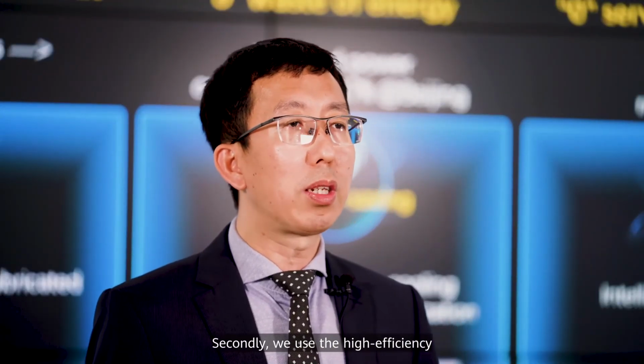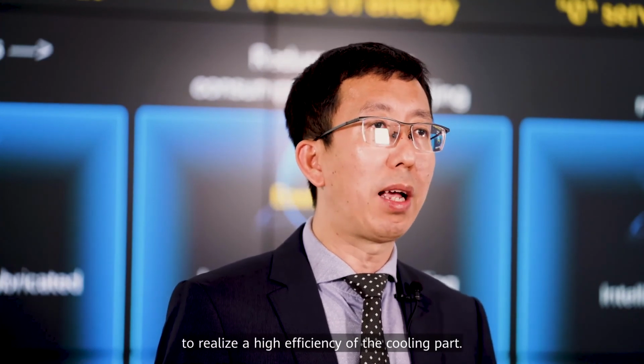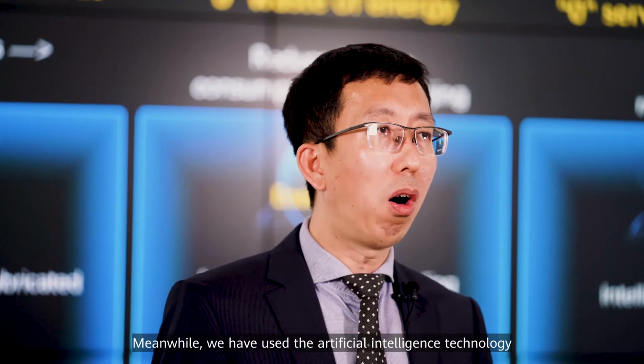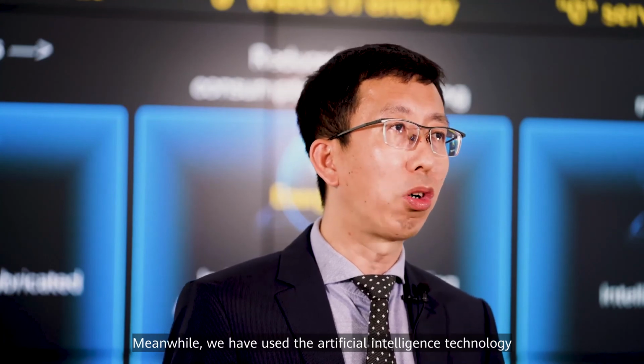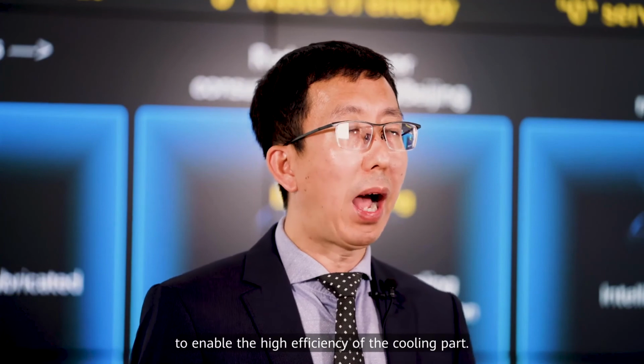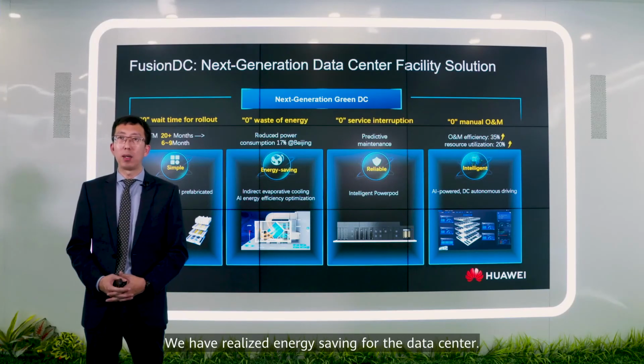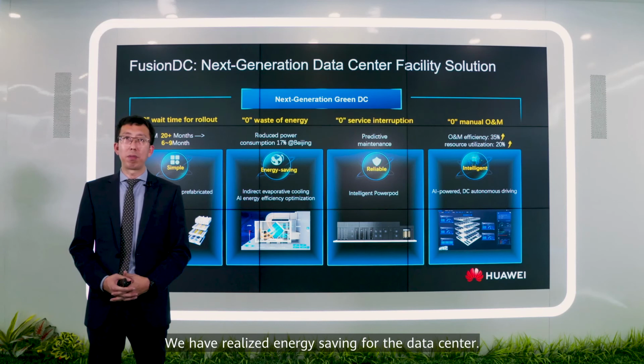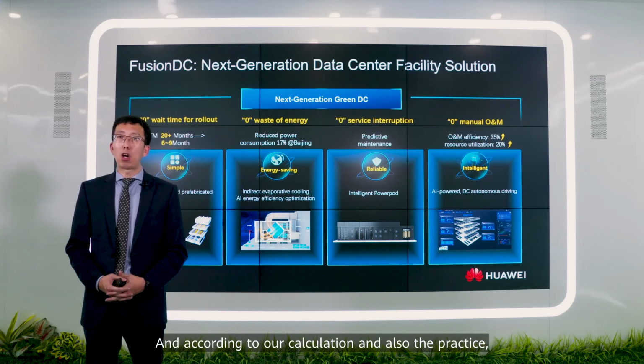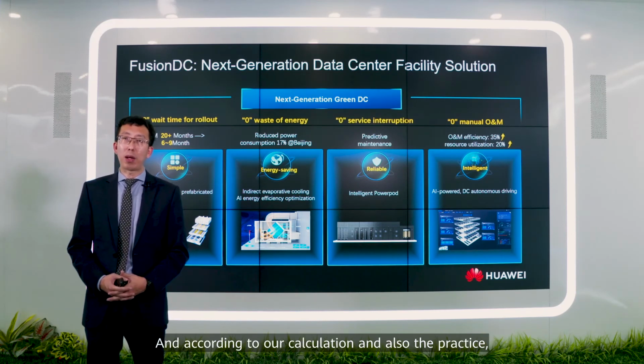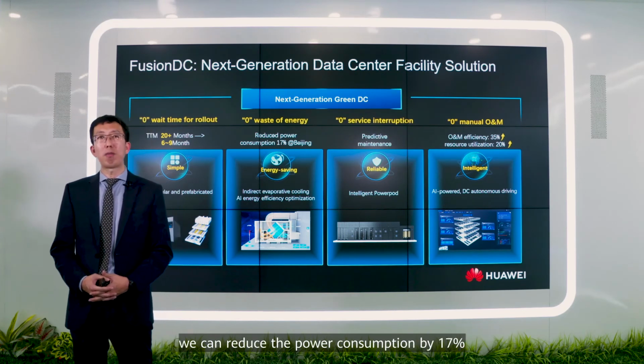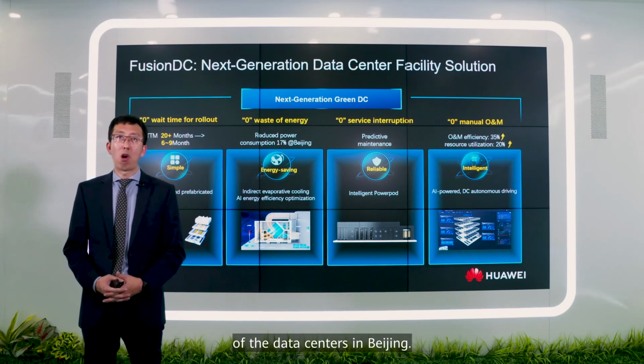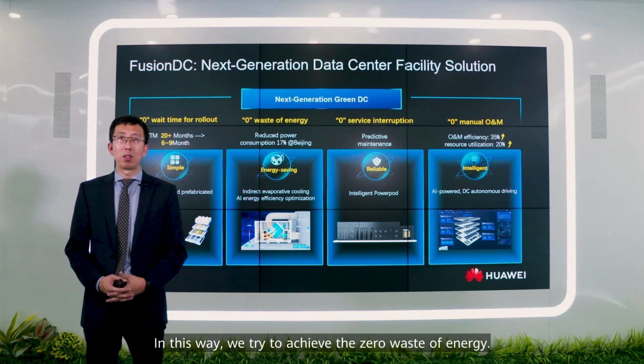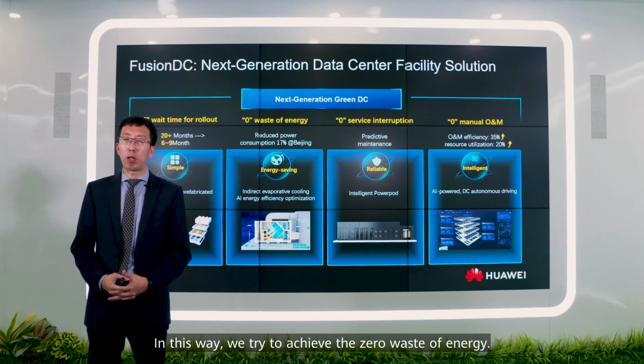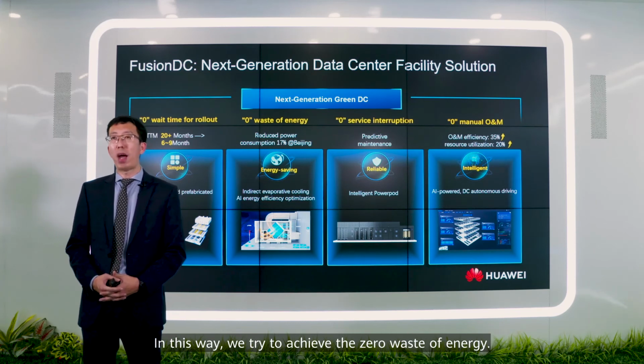Secondly, we use a high efficiency indirect evaporative cooling solution for high efficiency cooling. We also use artificial intelligence technology to enable high efficiency cooling and energy saving. According to our calculation and practice, we can reduce power consumption by 17% for a data center in Beijing, achieving zero waste of energy.